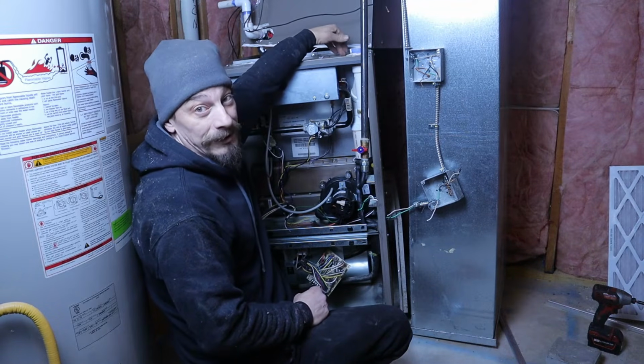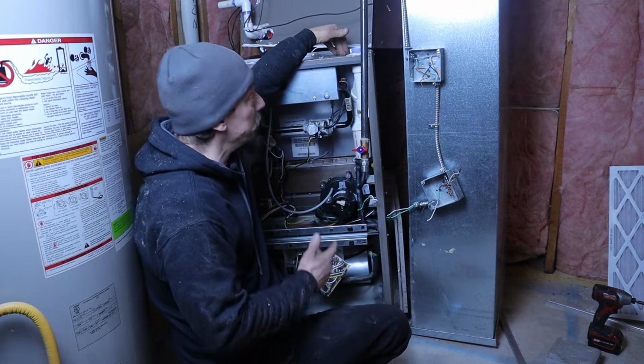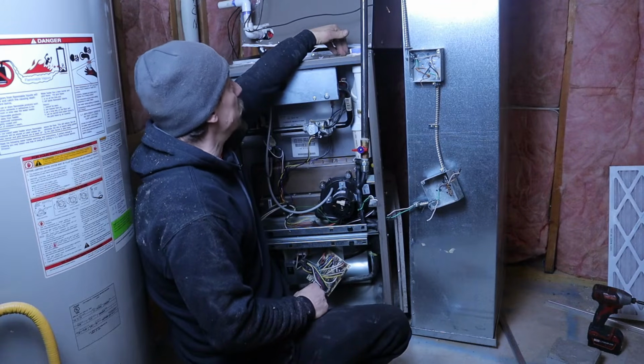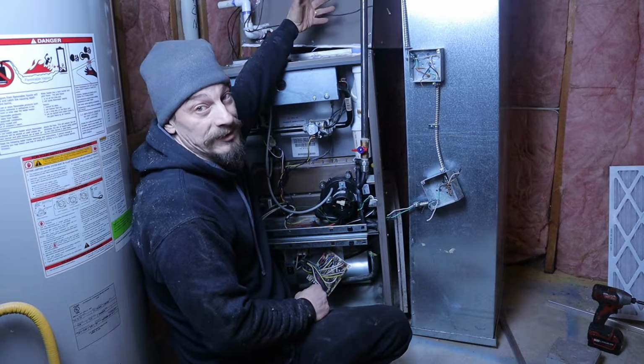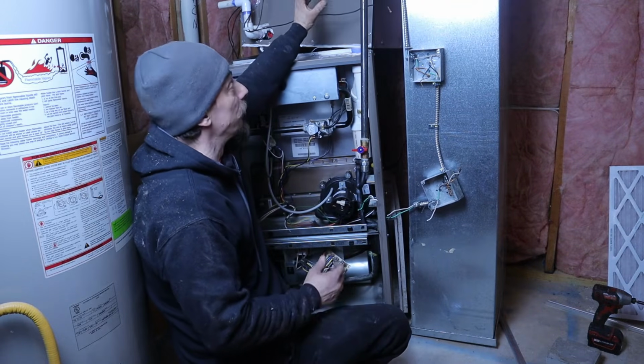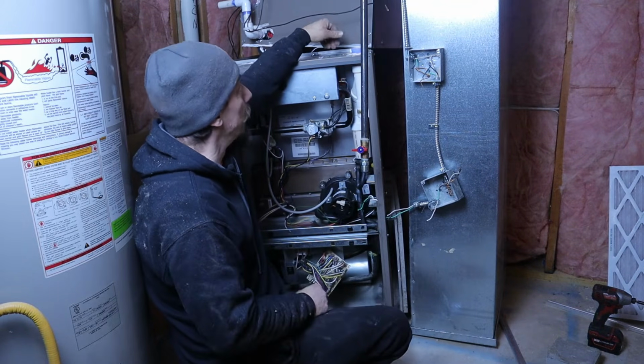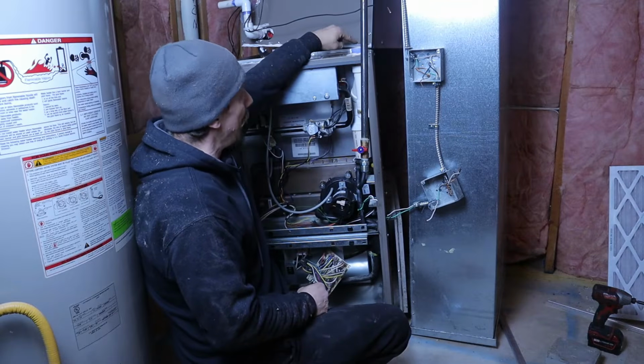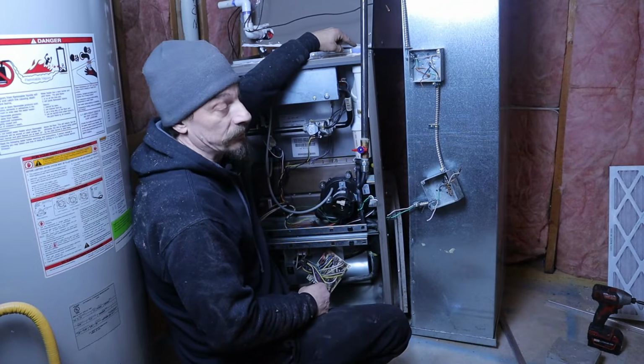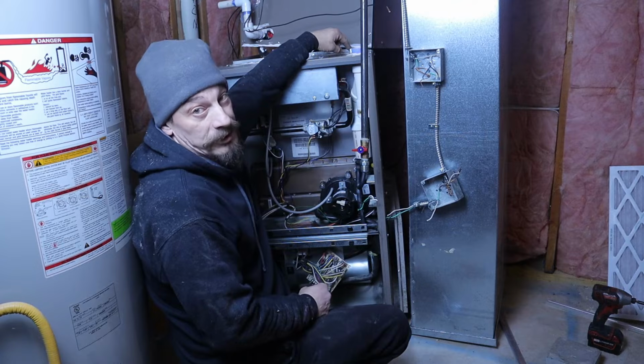Now it's kind of not good for us because we don't want to get into removing the coil out, because that's like an additional 3 hours of work. You have to pump the system down. It's a lot of work. So what we're going to do is that we just have one screw here. So we're just going to take a Sawzall with a metal blade and just cut that screw.